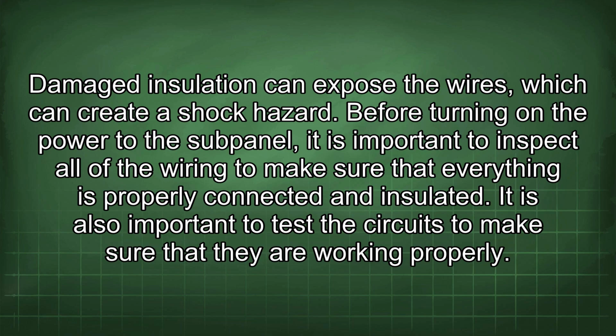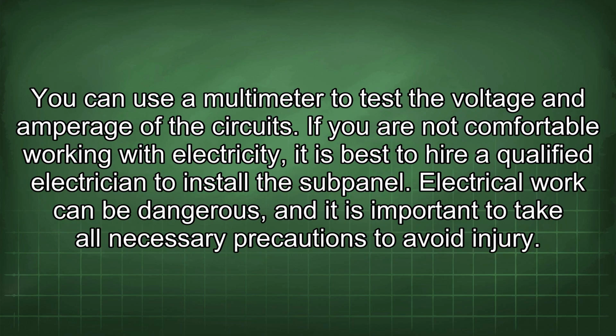Before turning on the power to the subpanel, it is important to inspect all of the wiring to make sure that everything is properly connected and insulated. It is also important to test the circuits to make sure that they are working properly. You can use a multimeter to test the voltage and amperage of the circuits.